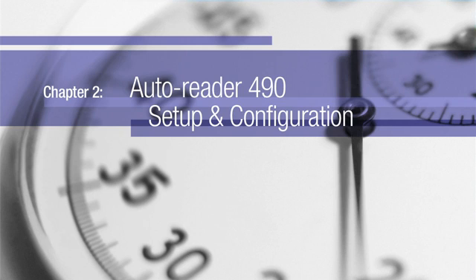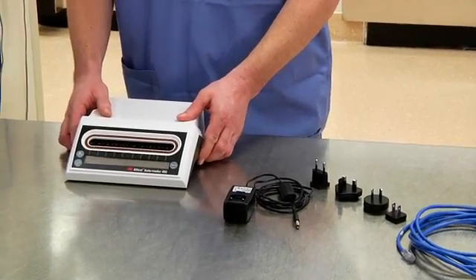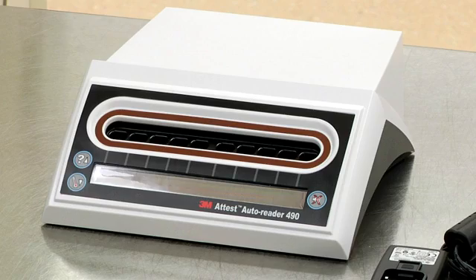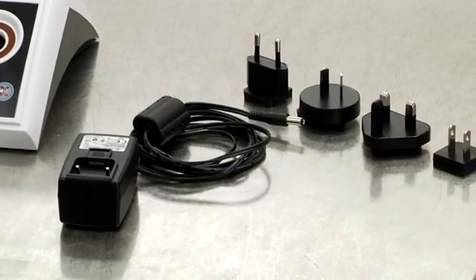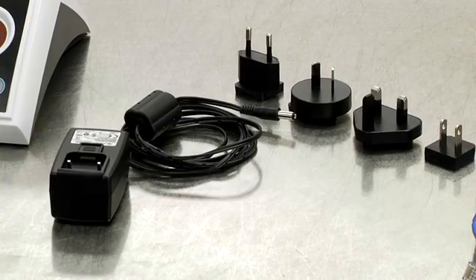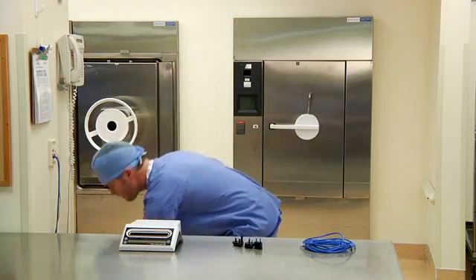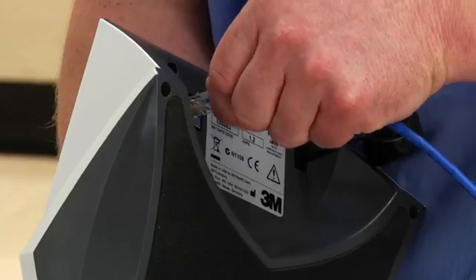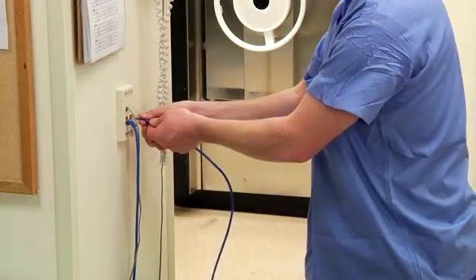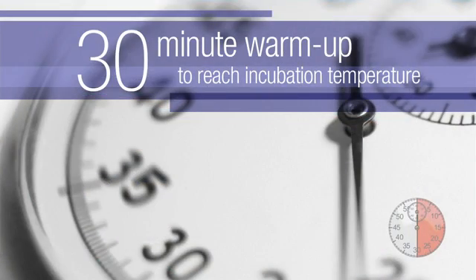Setting up and configuring your 3M Attest Auto Reader 490 is simple. First, place it on a firm level surface near an outlet, away from sunlight and incandescent light. The Attest Auto Reader 490 comes with multiple power plugs for use in different countries. Select the plug appropriate for your country and insert it into an AC-grounded outlet. If you plan to use the Attest Web App, connect the supplied Ethernet cable to an Ethernet jack. Once the unit is plugged in, allow it to warm up for 30 minutes.